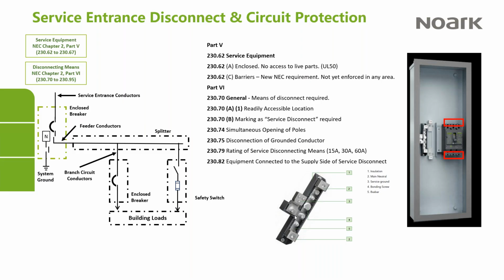In the case of this particular neutral assembly, the bolt that runs right in the middle of the neutral goes through the insulator and screws into the back of the enclosure. And this is what bonds the neutral assembly to the ground of the system. Okay. So that's one very misunderstood part of enclosed breakers in service entrance.